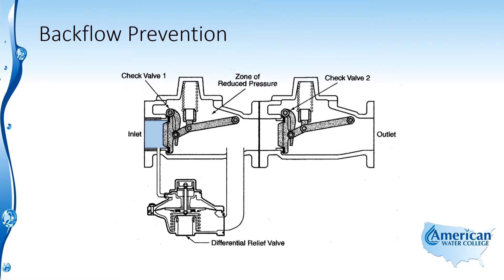In this type of valve, pressure flowing through the valve in the normal direction provides system pressure to the top of the diaphragm of the relief valve, and this keeps the relief valve closed. Should system pressure drop such that the spring pressure of the relief valve can overcome system pressure, air is allowed in because that relief valve opens, creating an opening between the two check valves, causing them to shut. That area is vented to atmosphere, creating an air gap — shown here in green — between the public water system and the cross-connected system.